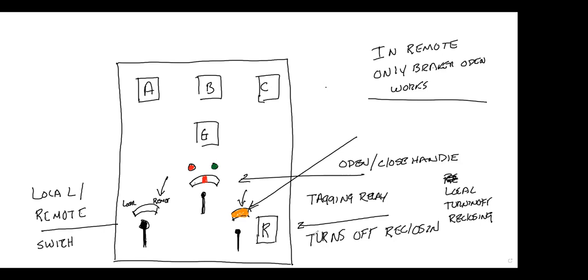You can sometimes, if they're doing it by SCADA, this handle moves by a motor. So even if SCADA does this, you should have an orange flag in here. In the wintertime, when it gets severely cold, that motor's not strong enough to turn it. They might send you to the substation and say, hey, we're not getting a non-reclosing indication. Can you check the flag? And it might only be halfway.